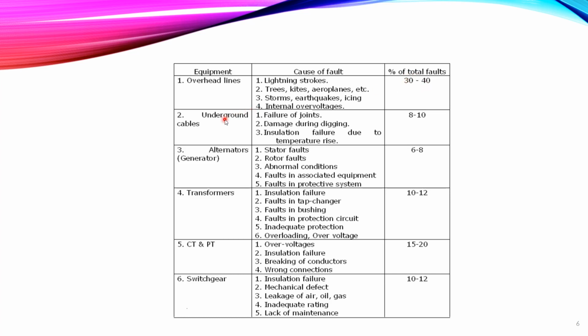The underground cables can have faults due to failure of the joints or damage during digging, for example, during construction or civil work, and insulation failure due to the temperature rise because the cables are underground. So if the temperature rises, then heat breakdown or insulation breakdown due to excess temperature will occur, which will cause, of course, the connection of the conductor with the ground. And this will cause 8-10% of the total faults.